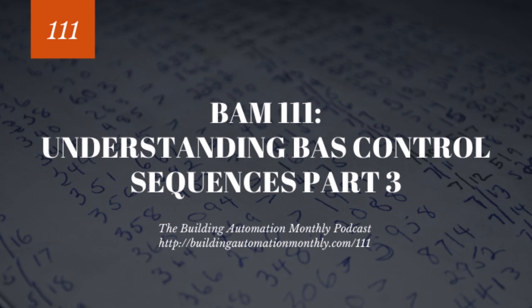And the easy way to remember that is you've got condenser water, so that comes out the condenser side. But essentially, in this refrigeration cycle, refrigerant changes state at different temperatures than water. So when you have a state change, you have a huge transfer of BTUs. You're taking advantage of this thing called state change when you change from liquid to gas, gas to liquid. And that allows BTUs to be absorbed and BTUs to be transferred.